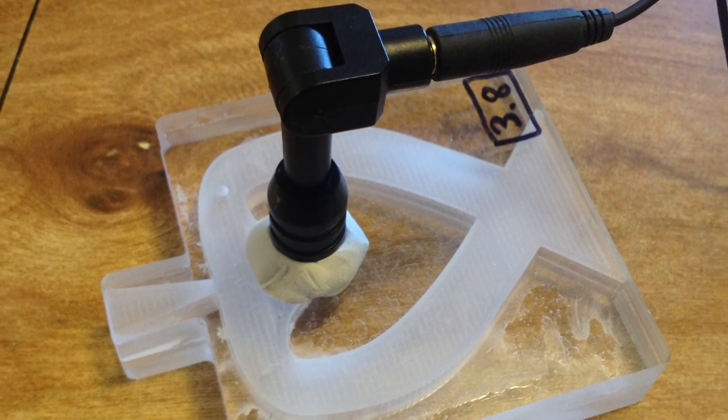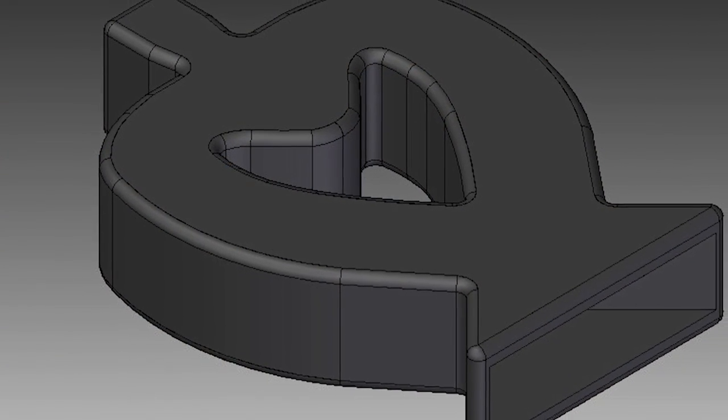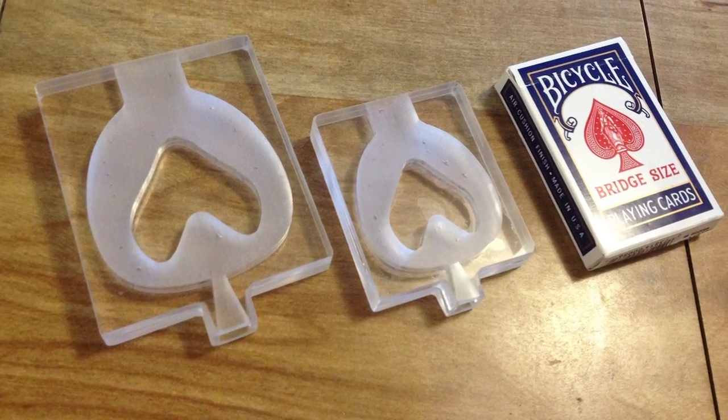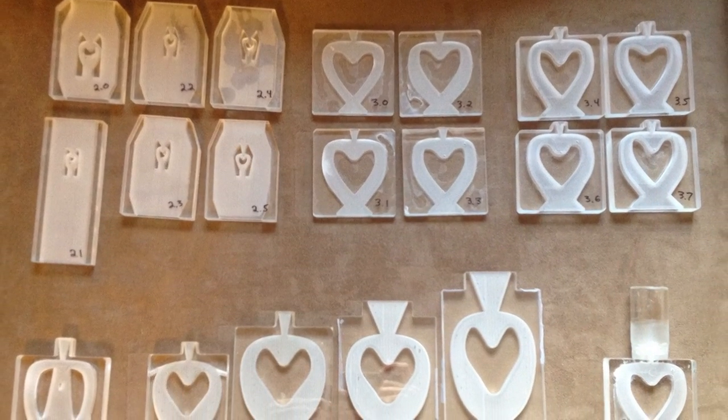The big barrier is that it's really difficult to use and it's very high cost, more between $1,000 to $3,000 for the average spirometer. What we were able to figure out is using a microphone as the main sensor for this device, and a specific mechanical channel to make the air actually oscillate back and forth without any sort of moving parts. Currently, our prototypes have been able to have comparable accuracy to those spirometers, which are thousands of dollars, but our production cost is under $10 right now.